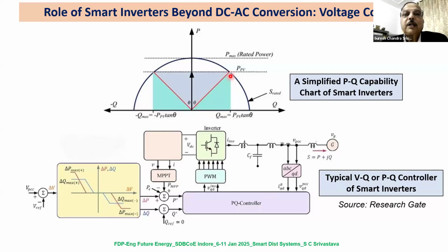So the same solar inverter, it is called a smart inverter, or the new concept that is coming, the grid forming converters. Grid following means that if the grid is there, the solar will operate. If grid is not there, solar will not operate if you don't have any battery. But grid forming will continue to operate, creating a reference voltage. So they will have this feature, and also smart inverters do have this feature. So reactive power control can be designed through converters.